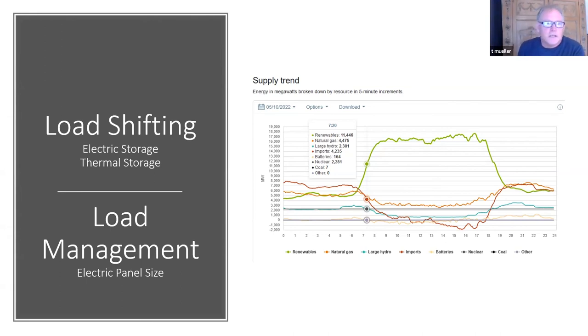What that does is allow you to prioritize loads so that you don't have the coincidence of high amperage loads simultaneously requiring a huge service. In my opinion, a single family home in the Bay Area should easily be able to operate on a 100 amp service and not have to go to 200 amp. Obviously there are some exceptions, but if you get heat pump installers out on the job site, or an electric vehicle added to the equation, people immediately say, oh my God, you need 200 amp service. I just don't think it's necessary.